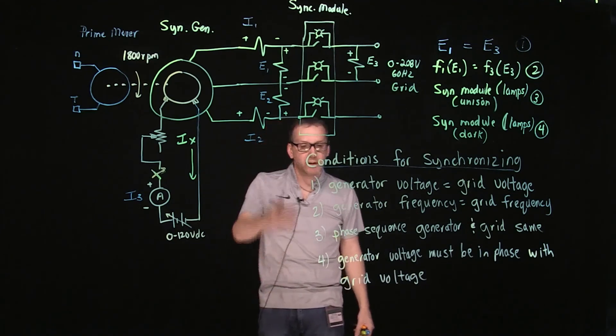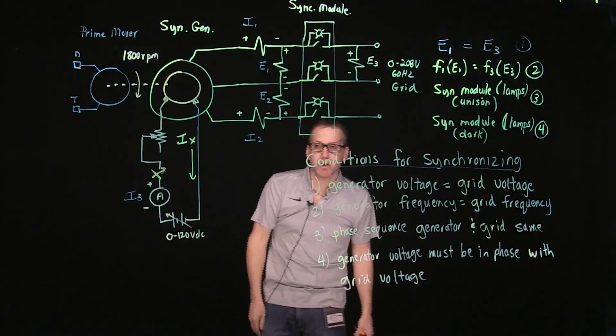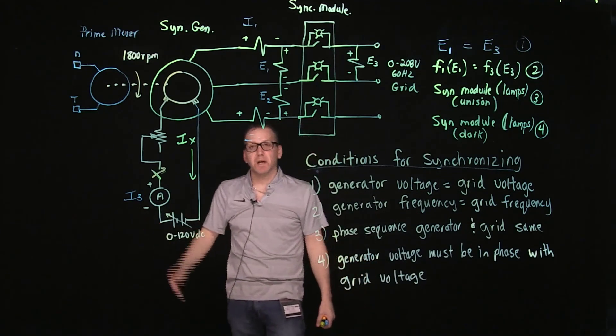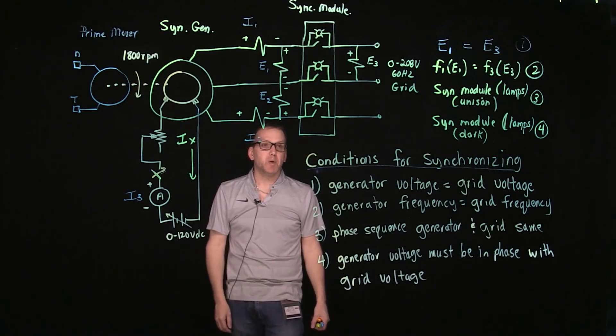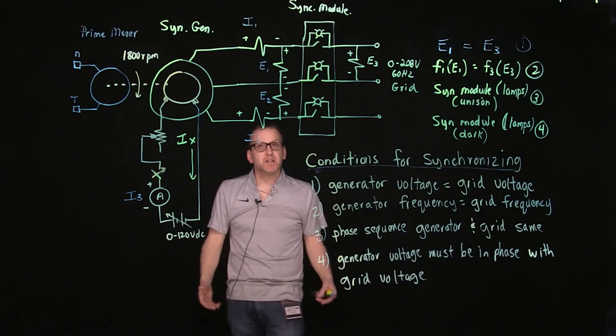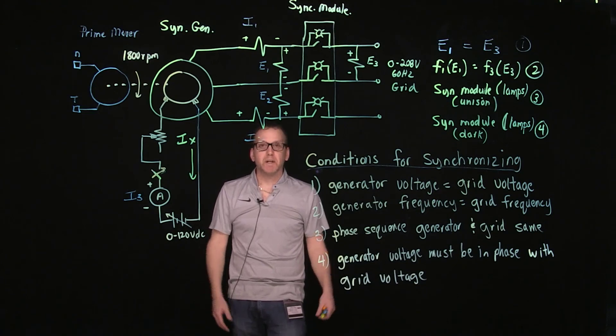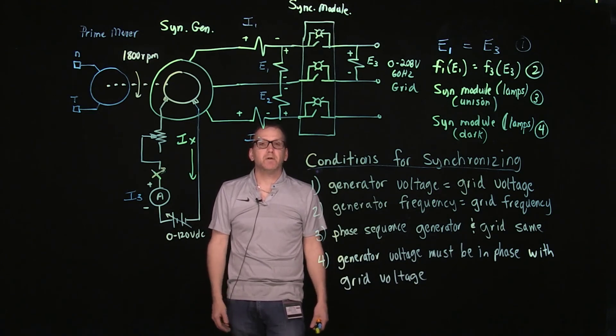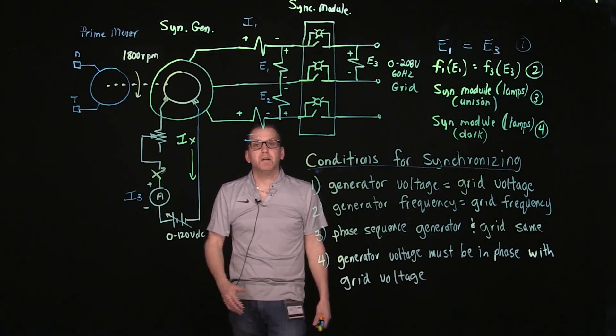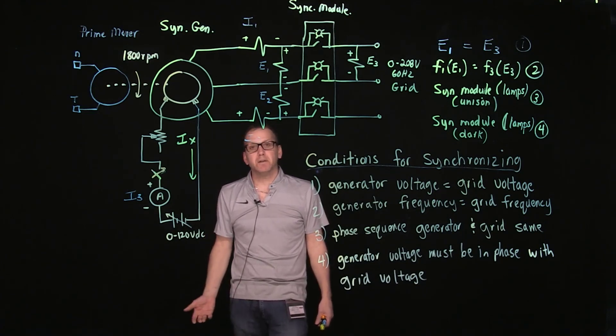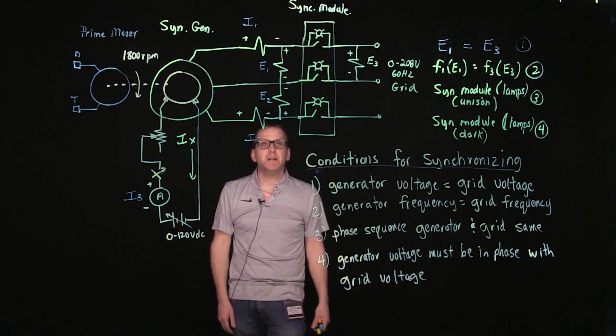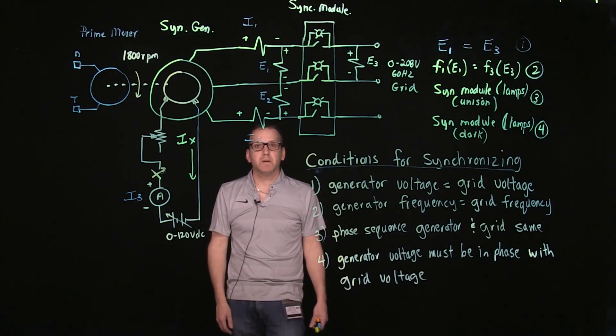The generator should now be synchronized to the infinite bus. The condition it is in when it comes online is the floating condition — the generator is neither delivering nor receiving any real or reactive power.